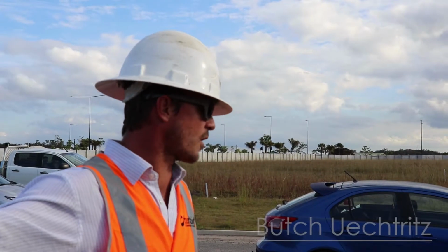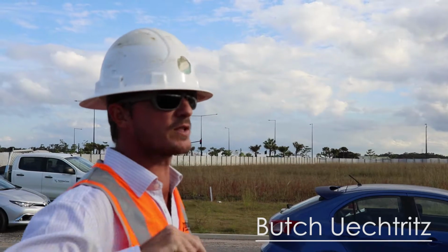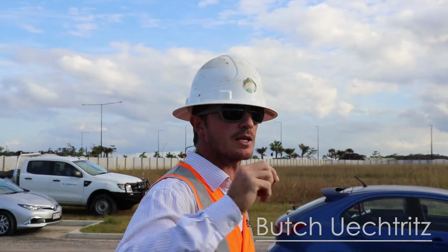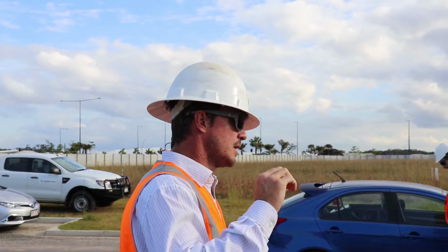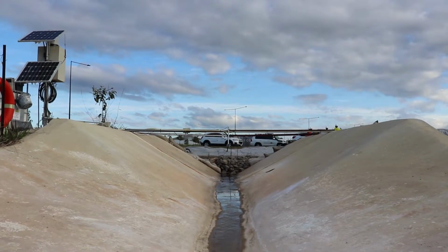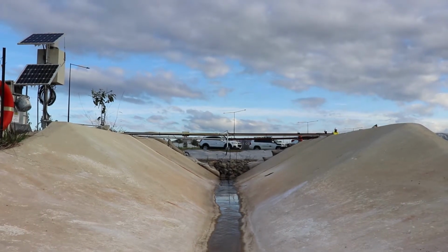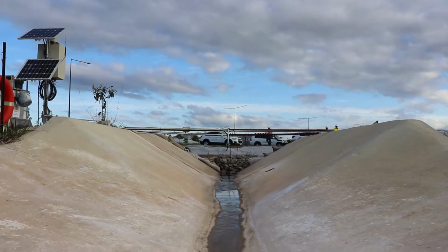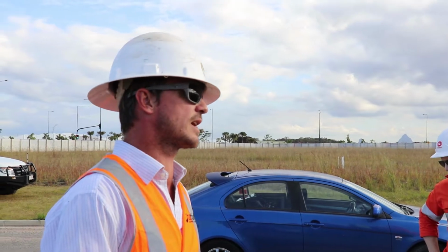So that's a flow-based system, and like Kyle was saying, that's really good for sites that really need to know what the volume's coming in. The channel there, converting that back to a flow, and then for a set volume that passes through it, it'll inject the coagulant to treat that volume.